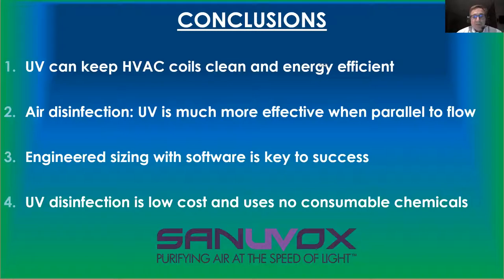Well, adding a biowall to a filtration system does not increase the pressure drop. It doesn't occupy enough cross section of a duct to have any significant impact on pressure drop. One thing you have to be aware of, some filters are not UV resistant because they're made with glue. Natural fibers are resistant. Fiberglass fibers can handle any kind of UV. Actually, UV doesn't go through glass. If you have a glass window, the UVC will not go through it. So fiberglass is very resistant for the same reason. But if the filter is made with polymer, the UV will damage it. So you don't want to expose the filters directly to UV light.